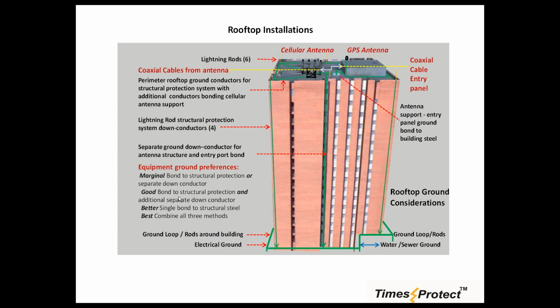I kind of want to make it fairly short. Marginal will be bond to structural protection or a separate down conductor. That will be the marginal grounding for towers, antennas, and infrastructure on the top of the high rise. Good will be bond to structural protection and an additional separate down conductor. So if you have structural protection, that would be better than anything else. Better will be a single bond to structural steel.